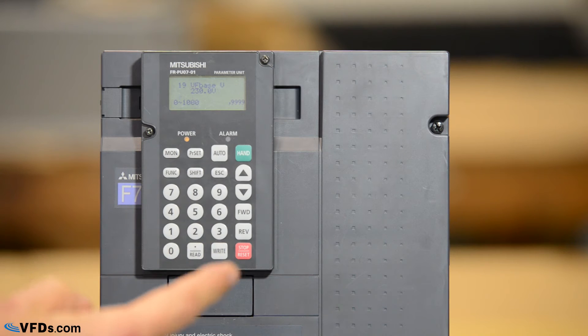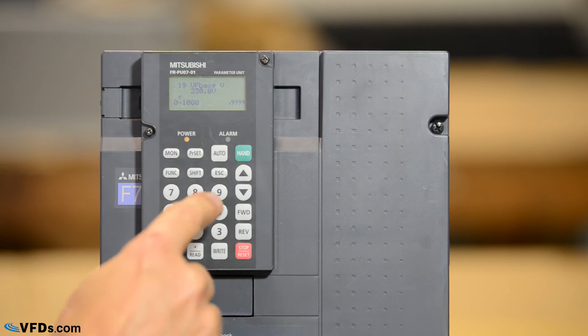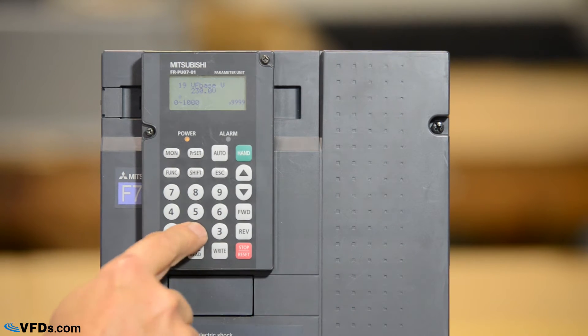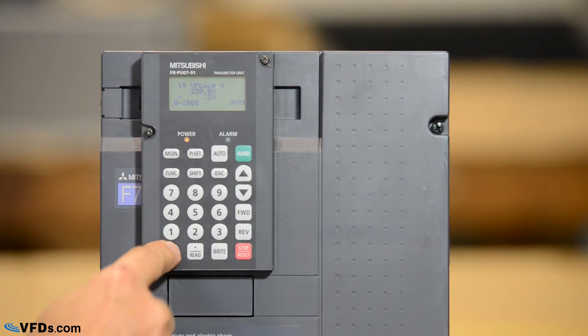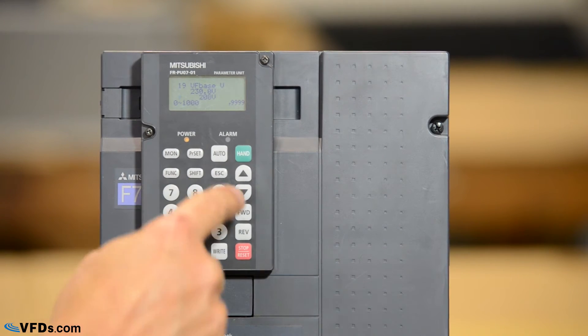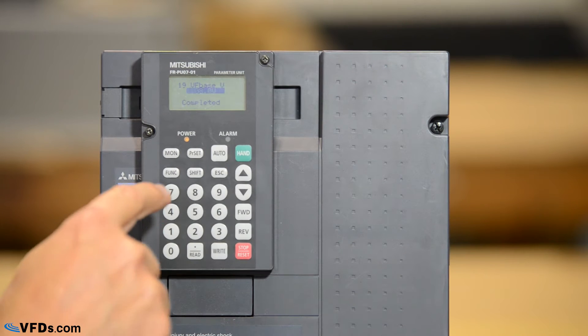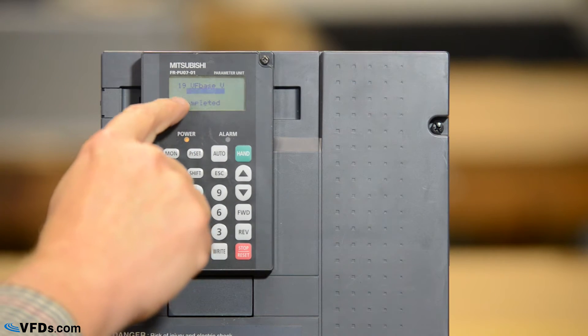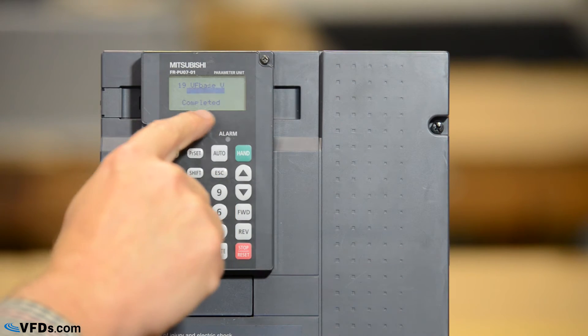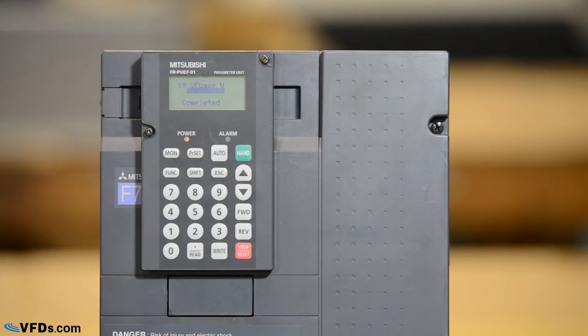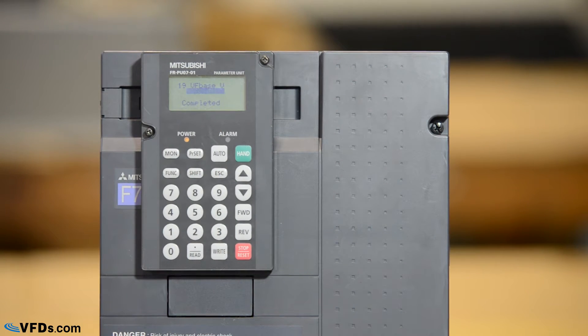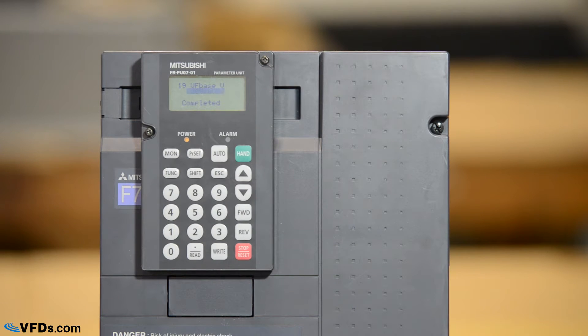My motor happens to be 208 volts so I'm going to type in 208 and then I'm going to push write. You'll notice that it flashes 208 volts and it says completed letting us know that that parameter has been changed.